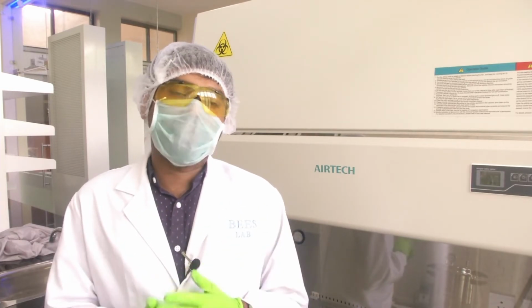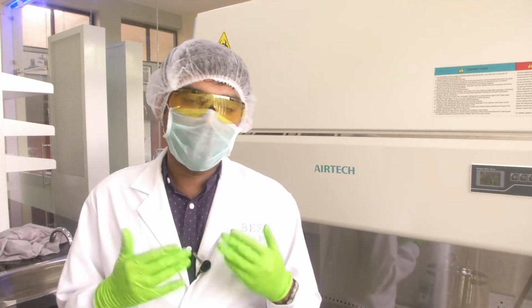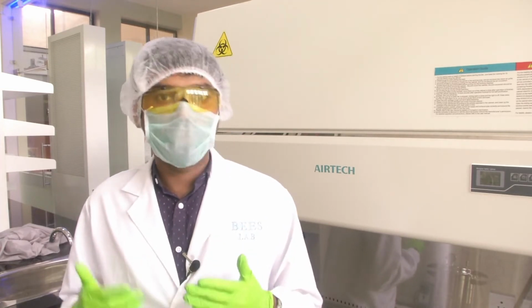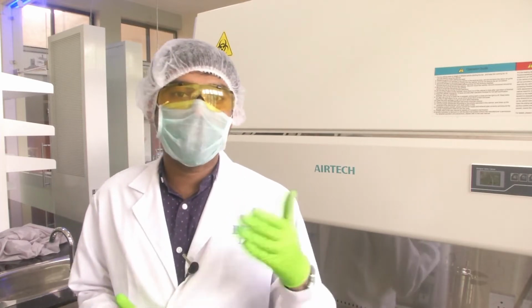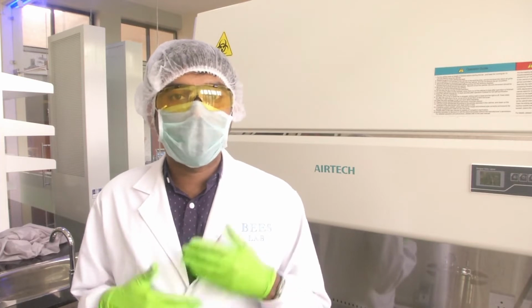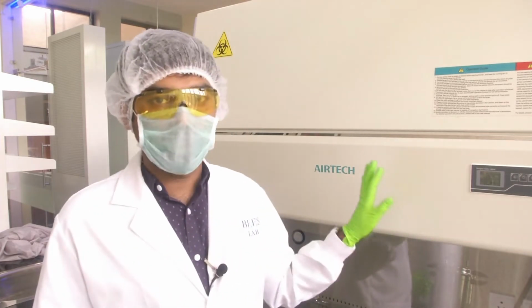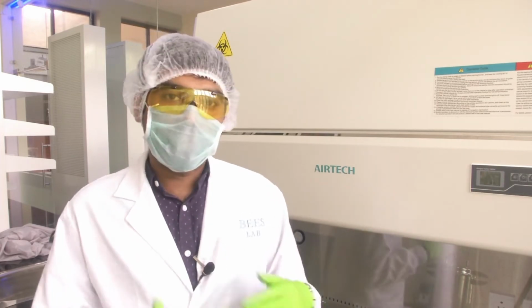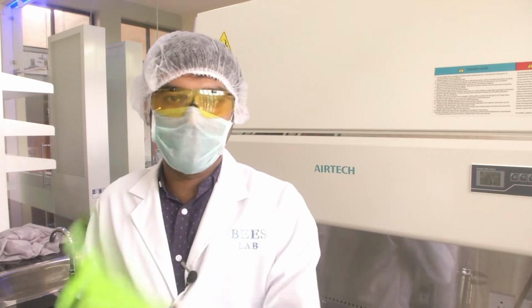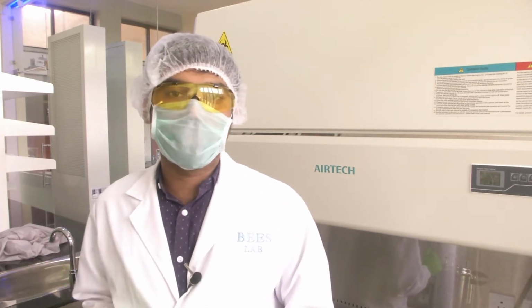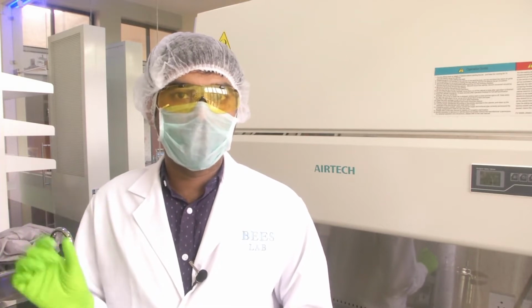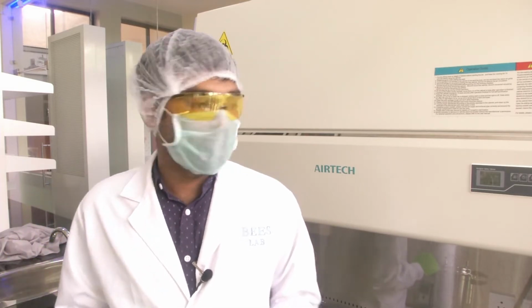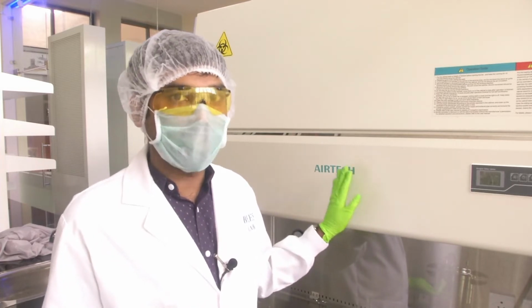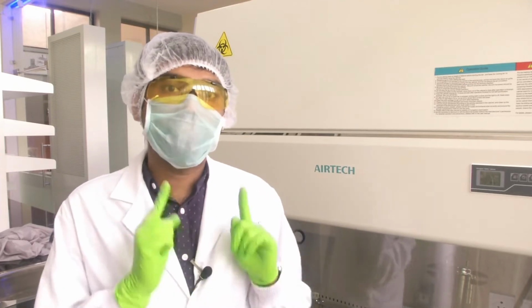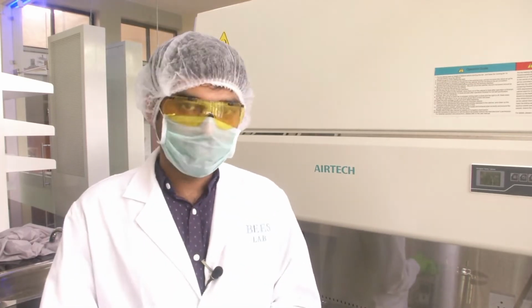As per a US standard, biosafety levels are classified into different types, like class 1, class 2, class 3, and there are set guidelines for each of these biosafety levels. As per each of these levels, there are also different types of biosafety cabinets. The biosafety level is called BSL, so we have BSL 1, BSL 2, BSL 3. This biosafety cabinet or biosafety hood is a BSL 2 equipment. What are these classes? I will get into it shortly.